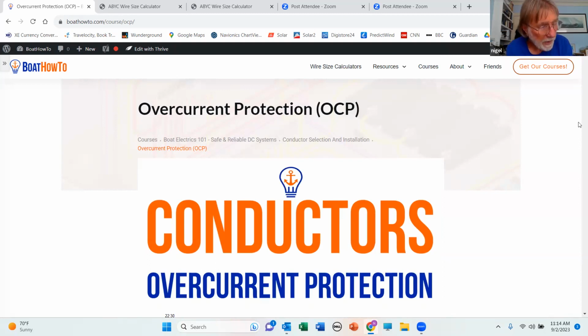One of the areas where you have a particular problem that's hard to address is with our shore power cords, because we cannot have a bolted connection at either end of the shore power cord, by definition, because the whole purpose of the cord is to be able to plug in and unplug when you get to a dock. So we've got a pin and sleeve connection, which is an inherently weak connection, especially over time, because the friction might reduce with use, and we're in a salt environment, we get corrosion, and then we get a little bit of resistance because of corrosion, and then we get an arcing fault, and then we start a fire.